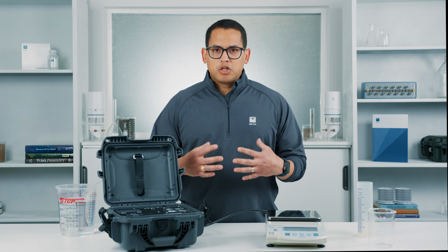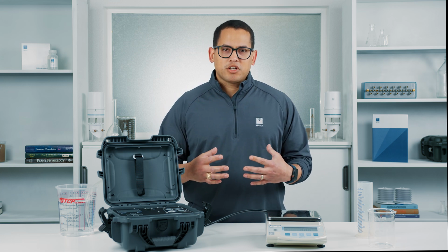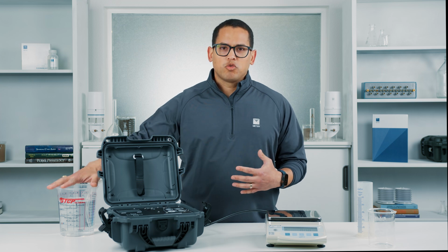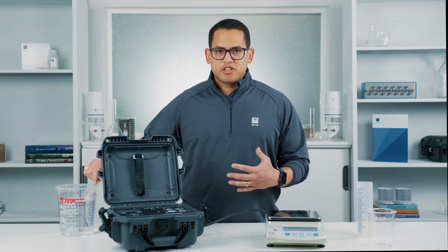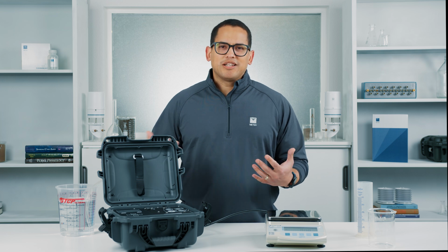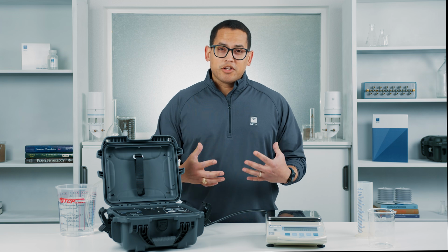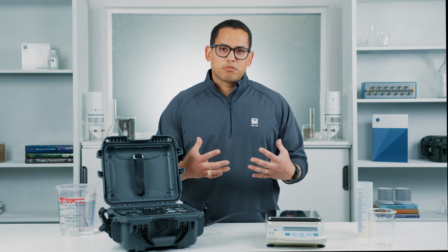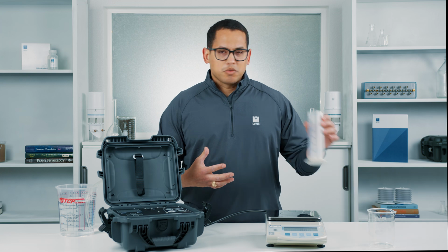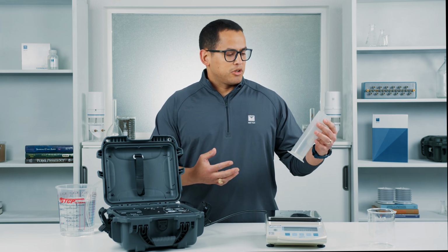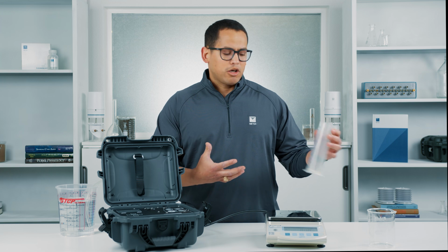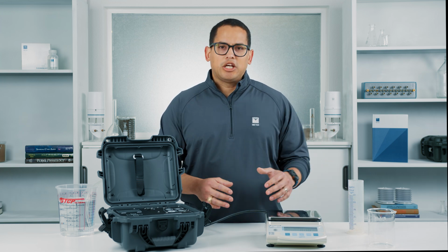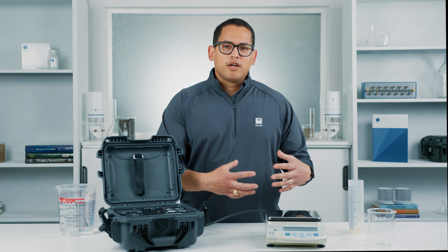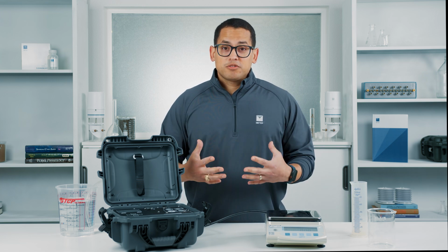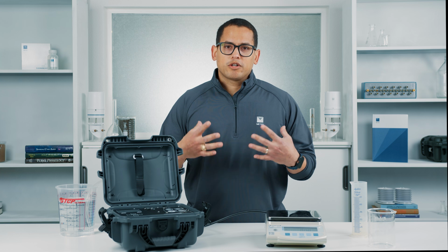But first off, it's important to note the items that you're going to need for the calibration process. The first thing you're always going to need, of course, is a source of water that's going to go here, and that's going to feed into the water supply line for the SATURO. I recommend at least 1 gallon of water for this process to purge the line and do all the things that you're going to need to do. And then depending on the two methods that you choose to use for the calibration process, you'll either need just a graduated cylinder like this for calibrating the SATURO based on the volume of water that's coming out, or you will need a scale and a container that can be placed on the scale to catch the water for the mass-based method. So the first method we're going to go through is the volume-based method for calibrating the SATURO device.